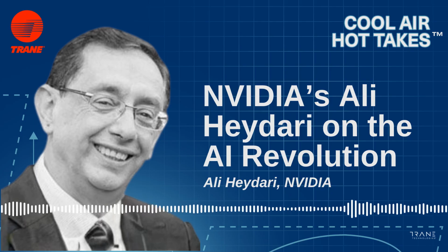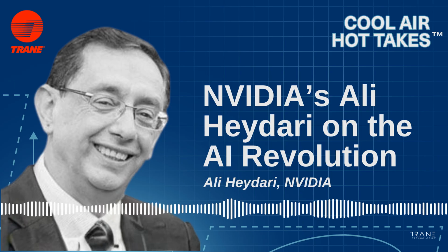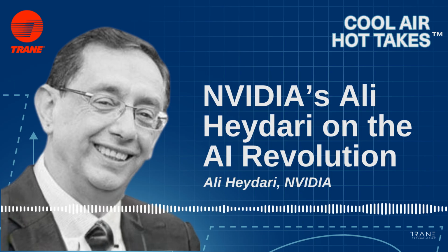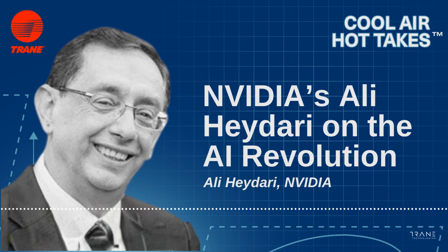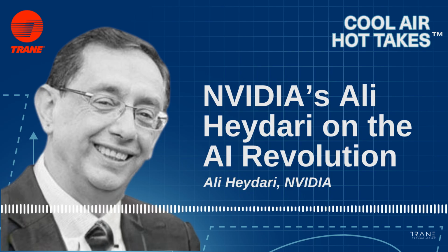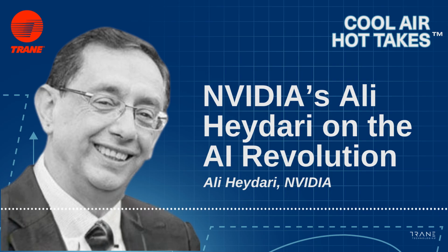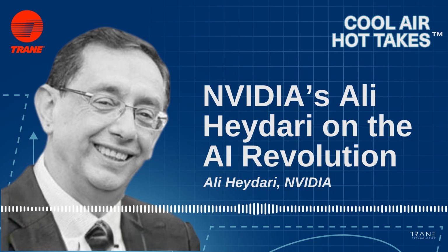If I have a gigawatt AI factory, if I'm spending 20% of the power on auxiliaries, majority of which is heat rejection through the chillers, CDUs, pumps, CRAHs and what have you, that means I have to put 200 megawatts reserved for a gigawatt of power allocated for IT. 200 megawatts today is bigger than most data centers that are built. When I was building a Facebook data center, they were like 50, 60 megawatts. So 200 megawatts is not something we can ignore.